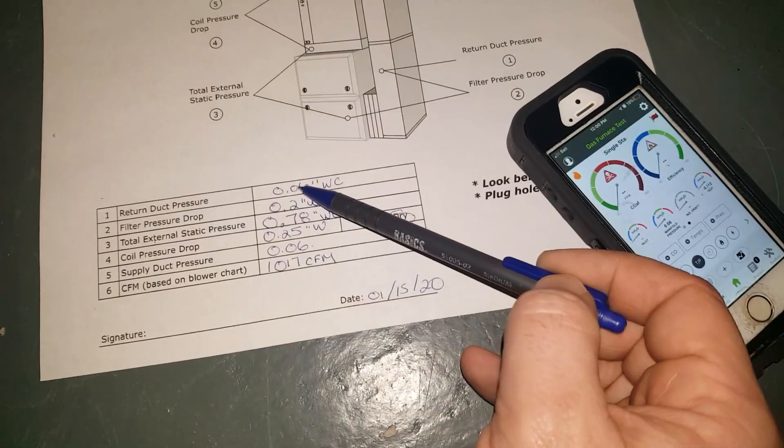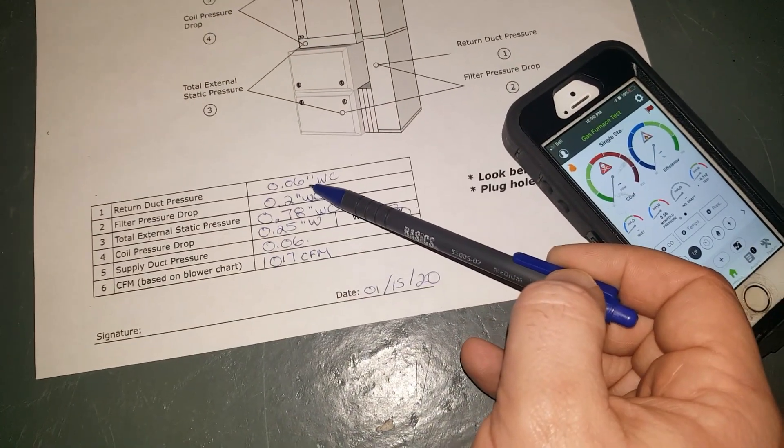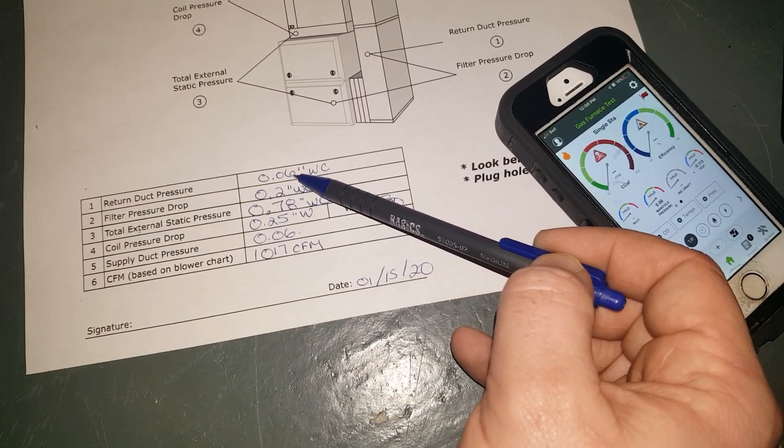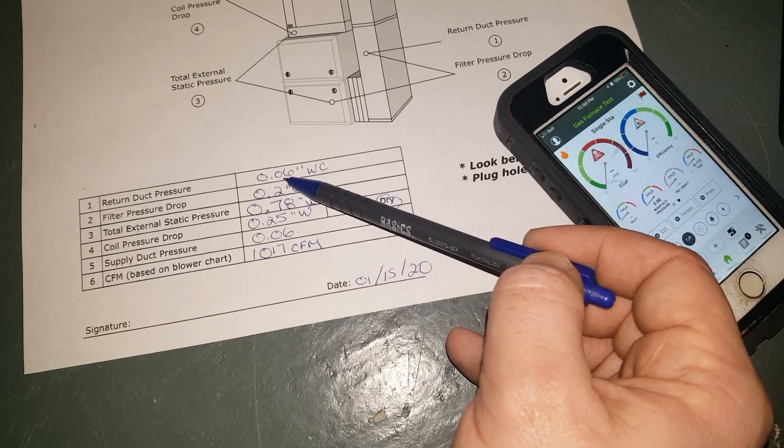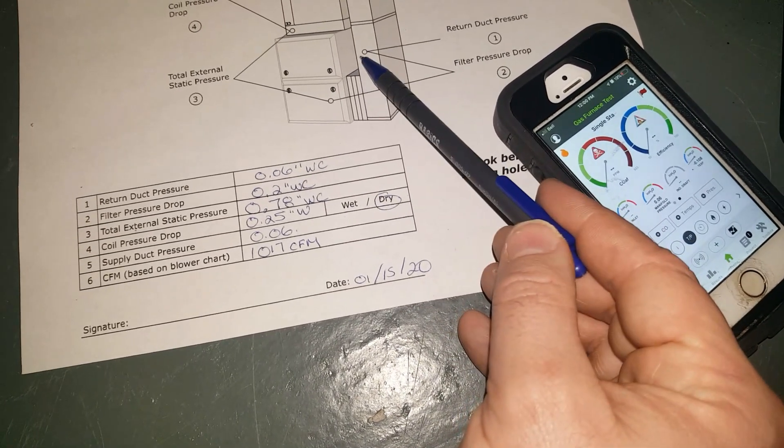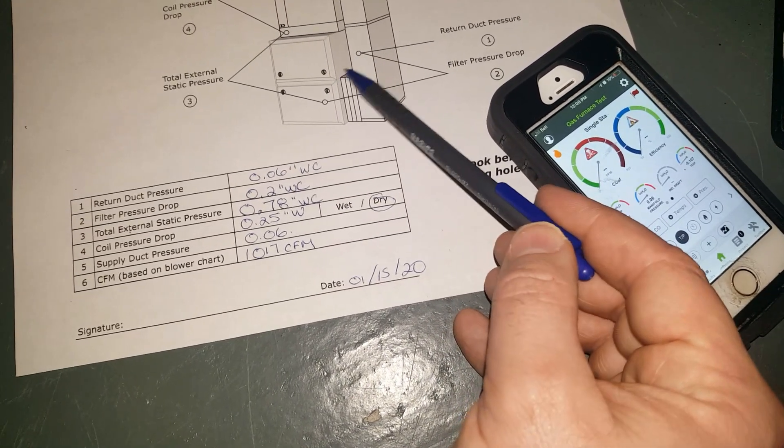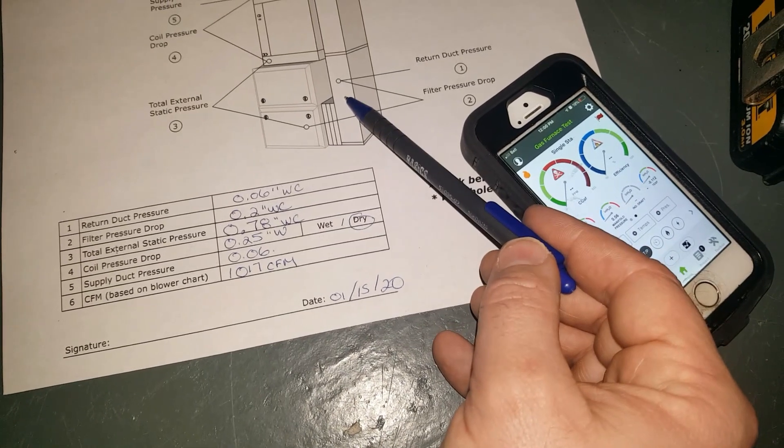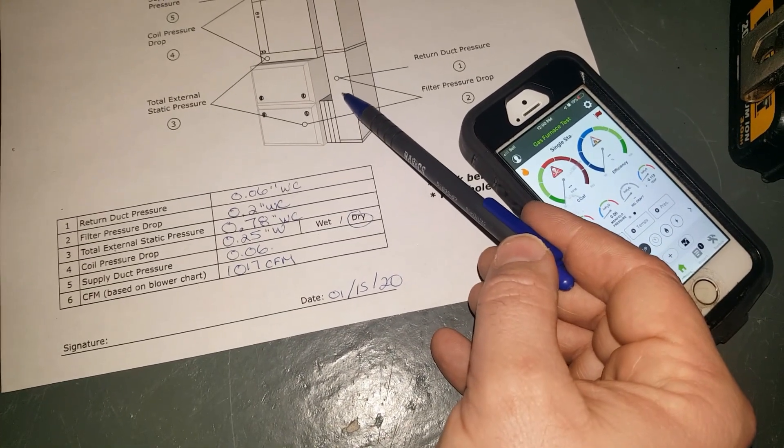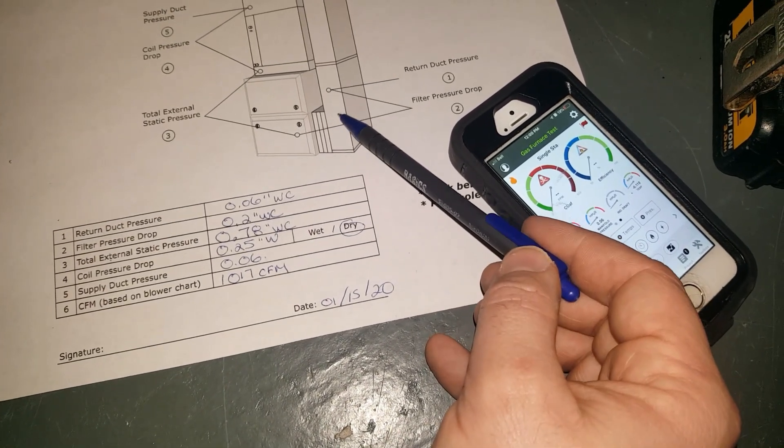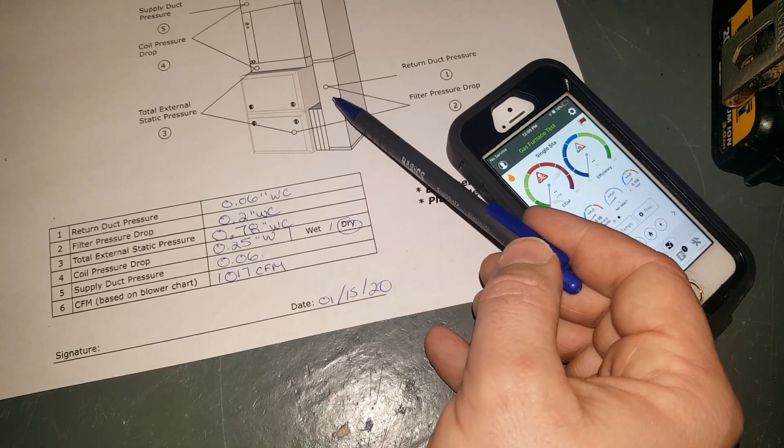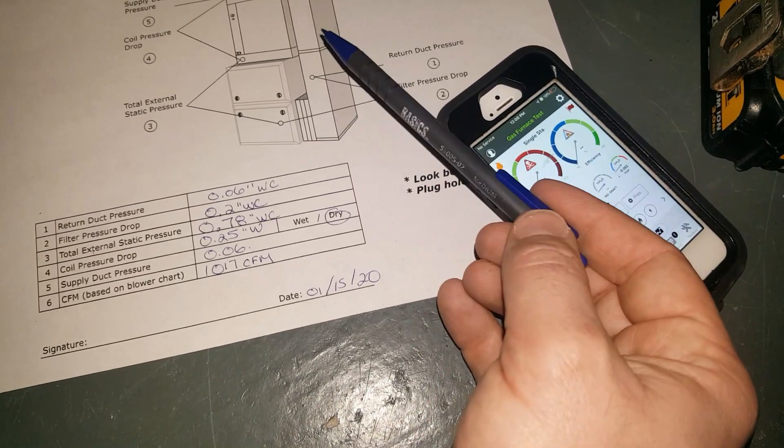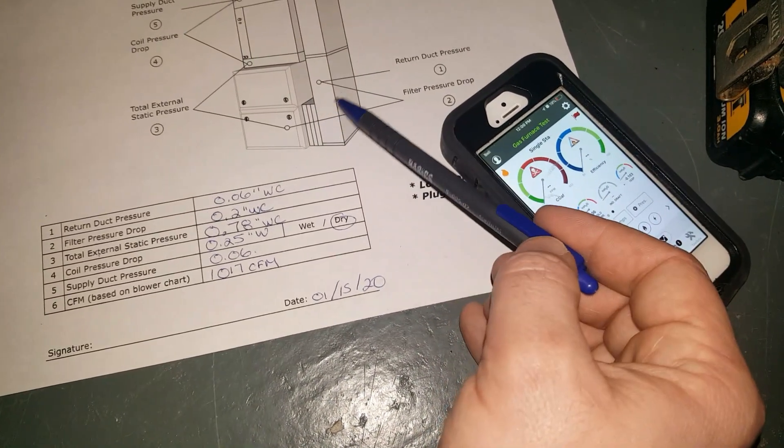Let's say for example our return side decides to go really high right here. Then I know I have to look and investigate what's changed. Do we have return issues, blockages, were renovations done, or any returns blocked?